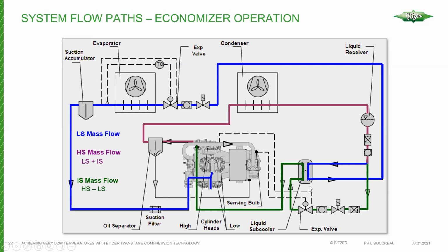So the purpose of that heat exchanger, which is a brazed plate heat exchanger, is to subcool that liquid. So we're going to refrigerate that liquid. And when we refrigerate the liquid, we've increased the heat capacity of the refrigerant. So if you take an extra 10 BTUs out of a pound of refrigerant, for example, before it enters the expansion valve, then in the evaporator, that same pound can absorb an additional 10 BTUs. And that's for a given compressor, a given displacement.